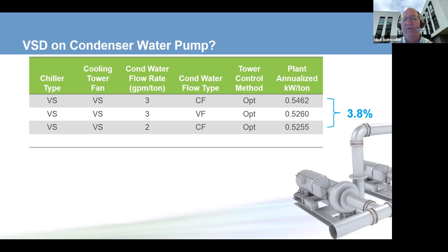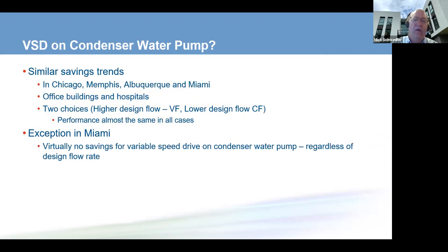Next, let's take it to the end. What happens if we both reduce the design flow rate and vary the flow rate? At that point, there are very little savings available. We've already gotten pretty close to optimal system operation with our design characteristics by reducing that condenser water flow rate. When we did this examination, we looked at it in four different climates: here in the upper Midwest, Chicago; Memphis, a more humid climate; a dry climate; and a hot and humid climate all the time. We did it for two different types of load profiles: hospitals that have a much larger, flatter load profile, and office buildings, which are more cyclical. And we did two choices, the higher design flow rate with variable flow or the lower design flow rate with constant flow. And the performance is almost the same in all cases. There was an exception in Miami because it was hot and humid. There was no savings at all for putting a variable speed drive on the condenser water pump.